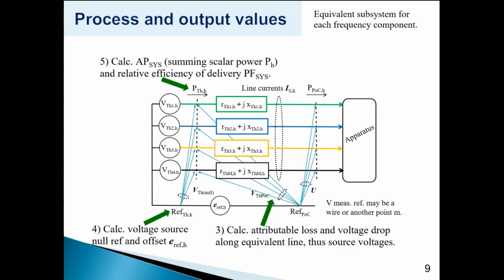There are several different methods of measuring equivalent impedances, and the voltage is derived from the impedance. So equivalent impedances, some of them are based on PMUs, others are based on passive change using Tellegen's theorem, and others are based on disturbing the load and then making the calculation. The most obvious case of that is when you do a short circuit and open circuit test on a transformer. You're disturbing the load and you work out the parameters of the circuit. Michelle Malengret has started production of some devices which measure the Thevenin impedances of the network to which it's connected, but there are probably 30 other ways of doing it.